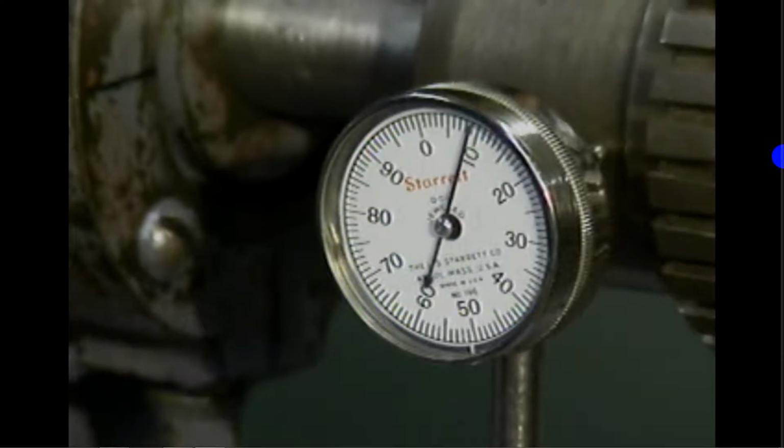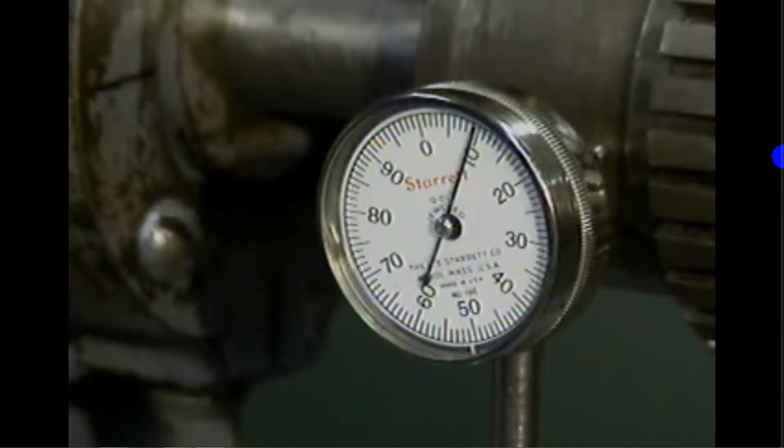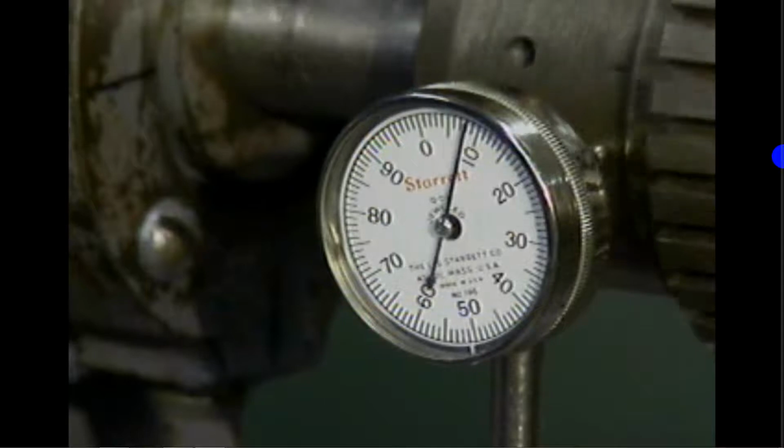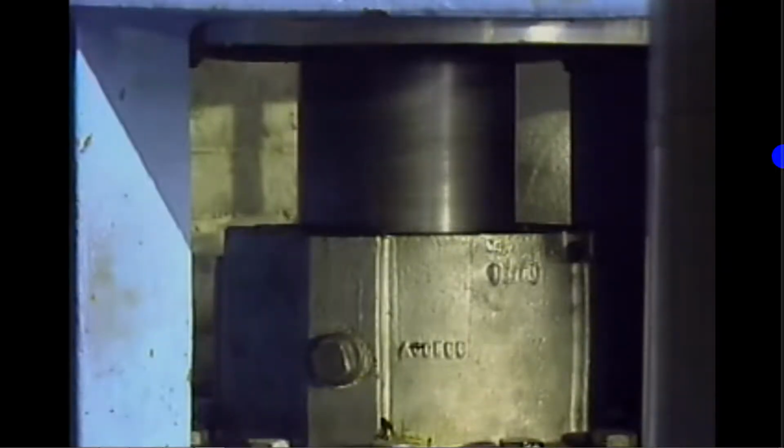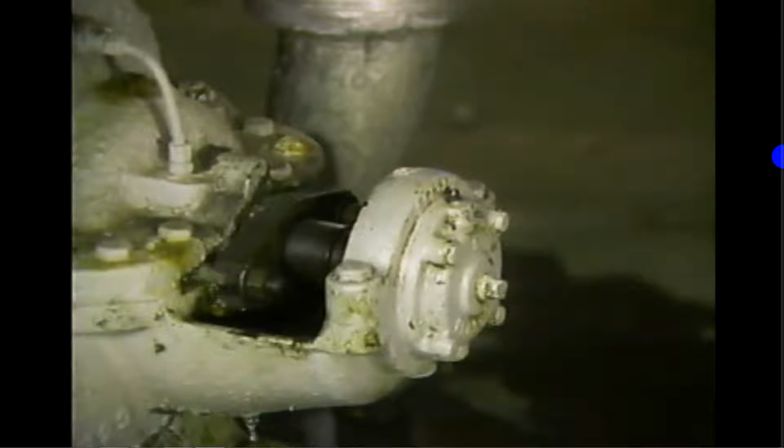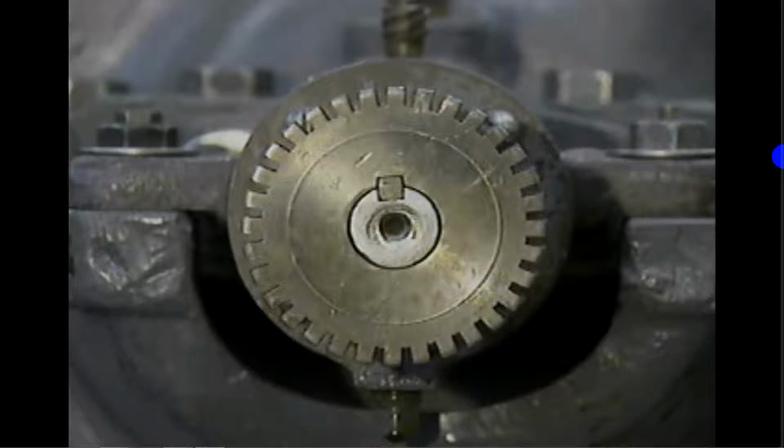A shaft typically has some runout or eccentricity during its rotation. However, too much runout is an indication of a problem. For example, a bent shaft or worn or damaged bearings could cause eccentric rotation of the shaft. A defective coupling that's out of round could also cause an excessive runout reading.